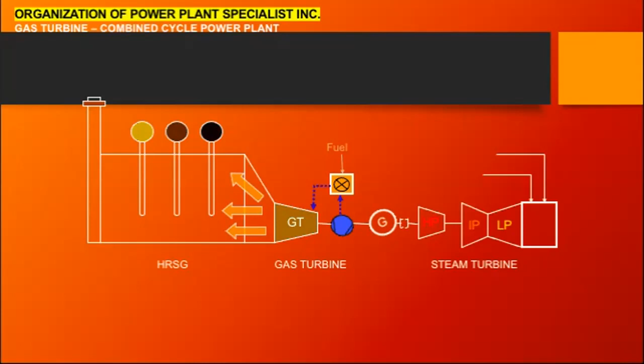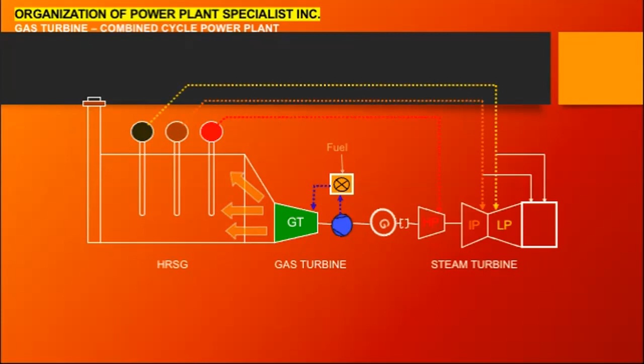Now, once all the burners of the gas turbine are flame on, the gas turbine speed is around 80% of its rated speed, and combustion is self-sustaining, the startup frequency converter will cut off once rated speed and synchronization are achieved. At this time, the steam turbine is still on turning gear, waiting for the correct steam quality and startup parameters. Once the conditions are met, the steam turbine will run up, and when it is almost at the rated speed, the synchronous clutch connecting the steam turbine side of the generator will engage, thereby increasing the generator output.